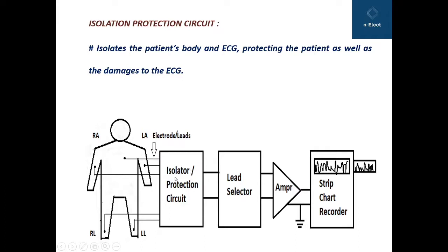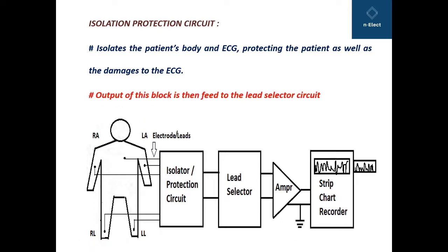The next block is the isolation protection circuit. It basically isolates the patient's body from the ECG, protecting the patient as well as preventing damage to the ECG — so it provides separation. The output of this block is then fed to the lead selector circuit.